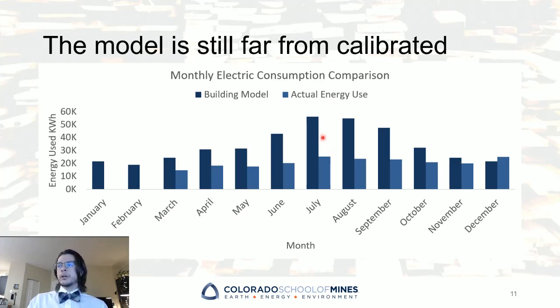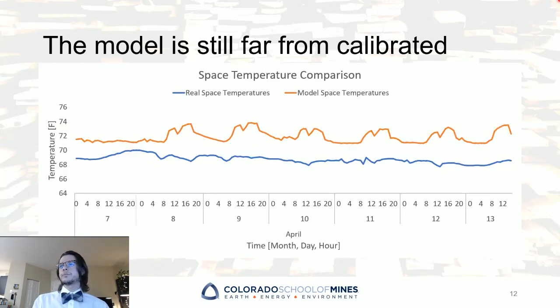But in the summer, the model is predicting much higher energy use than the building actually consumed in that year. So the target for the research right now is trying to look into how the model is cooling and trying to improve how well the cooling system mimics the actual building's cooling system.